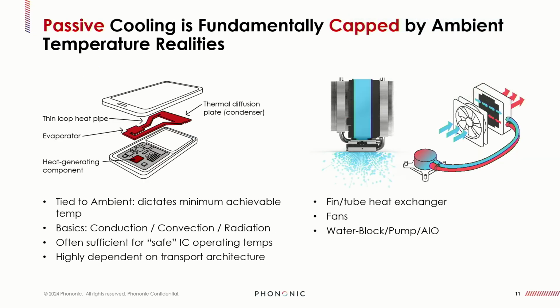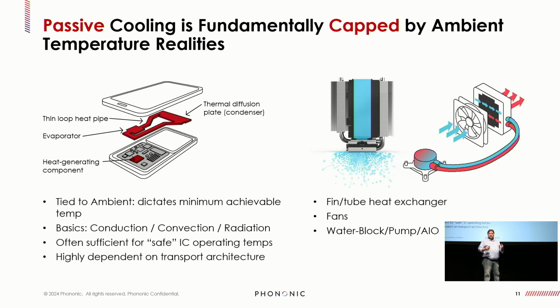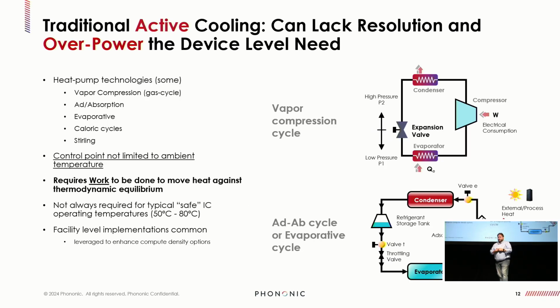So I want to distinguish that because there are some very real limitations to passive cooling. Fundamentally, they are tied to ambient or sink-source differentials, tied to the temperature around them. They can never reach that temperature - they will always be warmer than the temperature around them because they are passive methods. Doesn't matter if you use a heat pipe, a vapor chamber, single phase, two phase, conduction, convection, a pump, a fan - makes no difference. They're still passive and still limited in what they can provide.